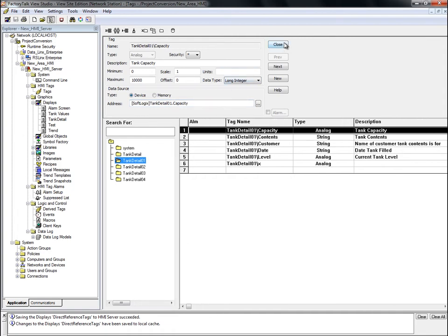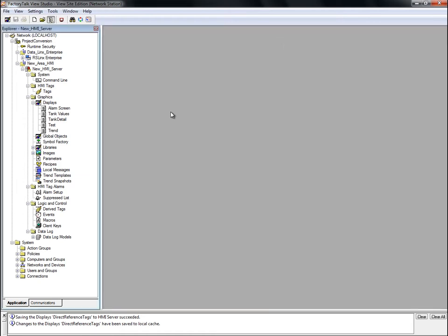It is a View SE best practice to create each server, data, or HMI in its own area. However, if you create your RSLinx Enterprise data server in the same area as your HMI server and configure your RSLinx Enterprise shortcut to use the same name as the RSView32 node, in this case SoftLogix, the device tags will not need to be reconfigured and will work as imported.